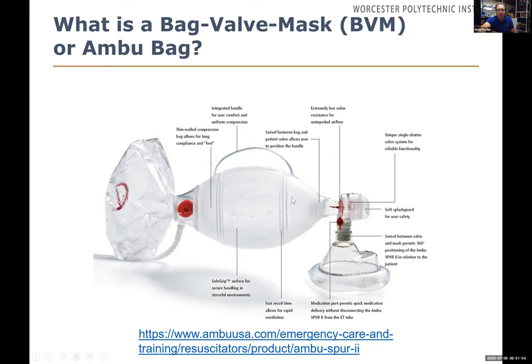The Ambu bag has filters, a CO2 sensor port, and PEEP valves to adjust residual pressure in the lungs. The mask can be replaced with an endotracheal tube for invasive ventilation. A key safety concern with infected COVID patients: these devices normally exhaust exhaled air into the atmosphere, which is a major problem. We focused on adapting these devices and creating 3D-printed components on the exhalation pathway to redirect exhaled air through a filter, without affecting the air going into the patient and without the same regulatory requirements.